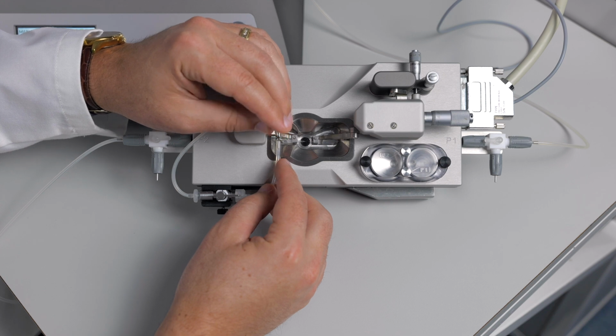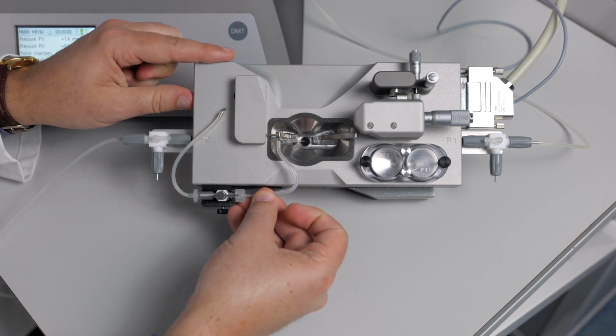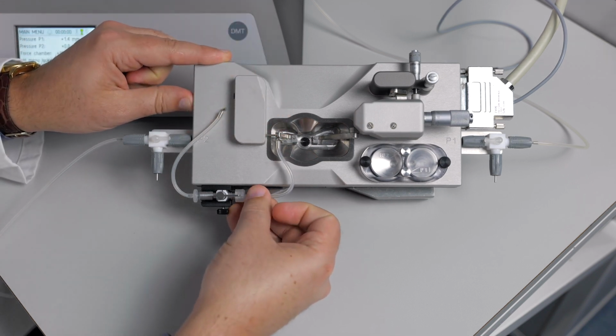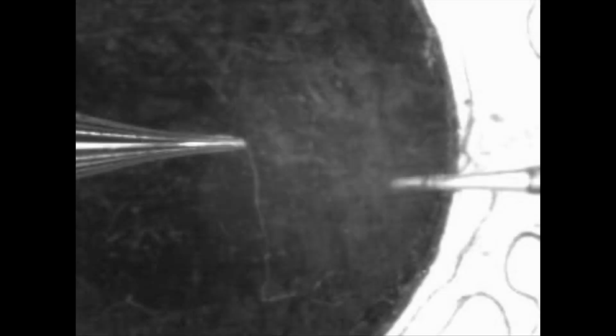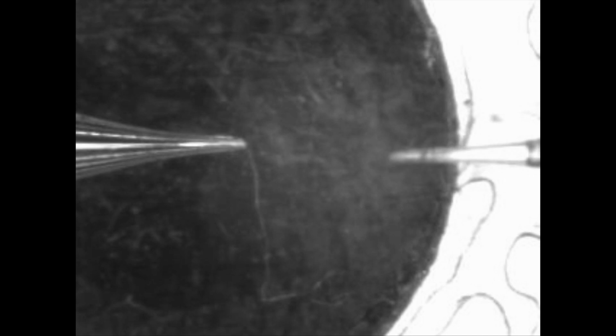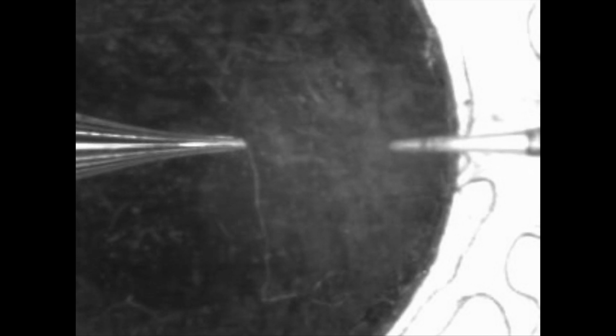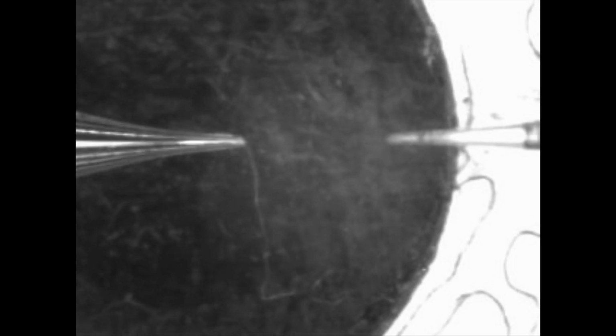Lastly, we will cover how to align the cannulas under the microscope. In order to get the most accurate cannula alignment, perform these adjustments under the dissection microscope. You can start by focusing your view on the P2 cannula, as this is fixed in place on the force transducer. You can then adjust the y-axis of the P1 cannula so that it appears to be in line with the P2 cannula. Then move the cannulas so their tips are close together.